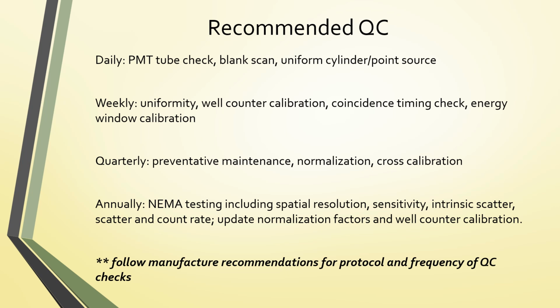Keep in mind the manufacturer recommendations and the protocols for these QC will change. They're very different based on manufacturer recommendations and frequency. So just a general overview. Daily, you will perform a PM tube check, blank scan, uniform cylinder, point source study. And then weekly, uniformity, well counter calibration, coincidence timing check, and energy window calibration.